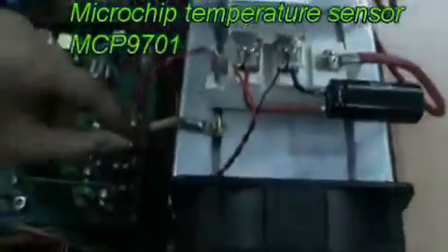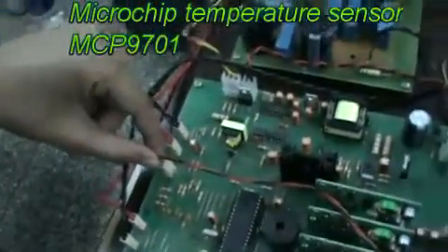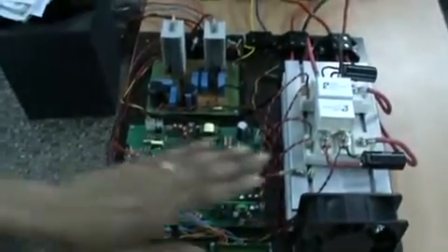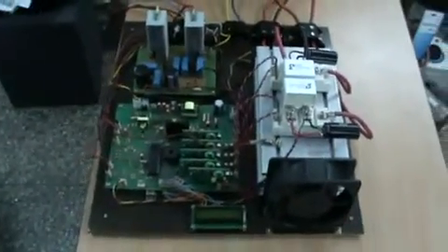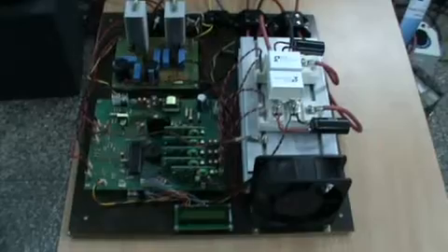The IGBTs are fixed on the heatsink and the temperature sensor is connected to the control card. When the heatsink temperature reaches the set value, the fan will be switched on, and the fan will be switched off when the temperature reduces to the preset value. The on-off control of the fan is done using a triac. The IGBTs are connected to the primary of the transformer. This is the battery connection. This is going to the secondary of the transformer.